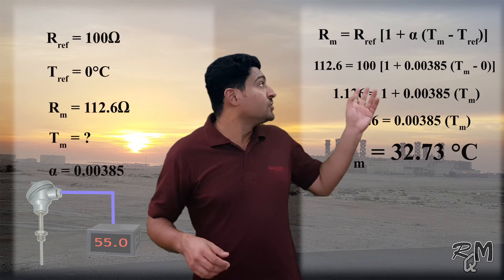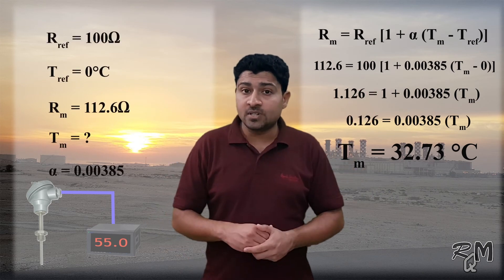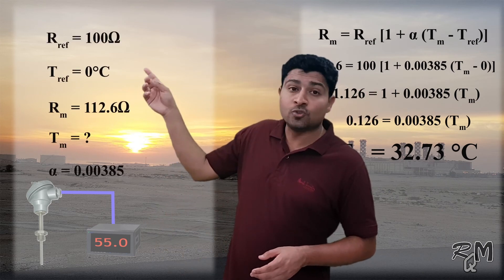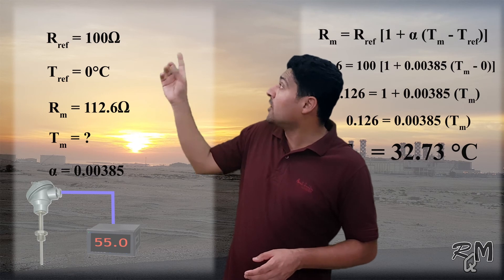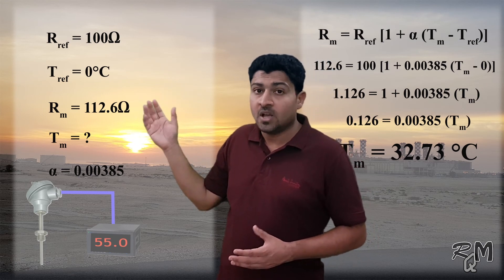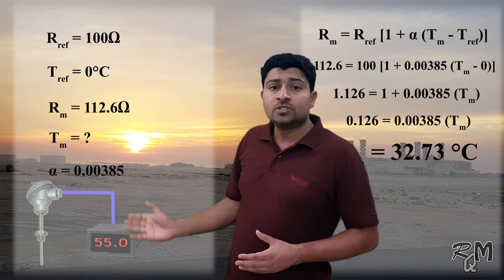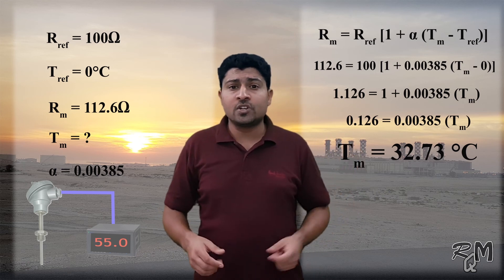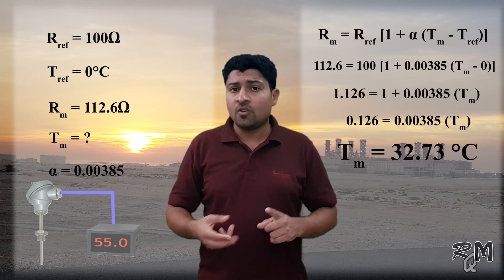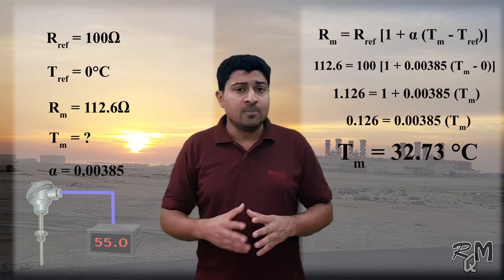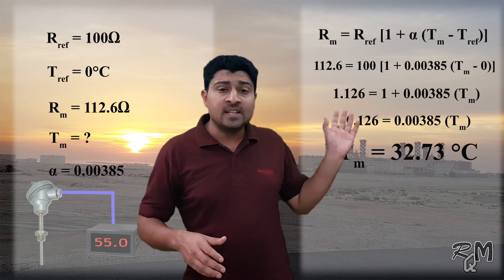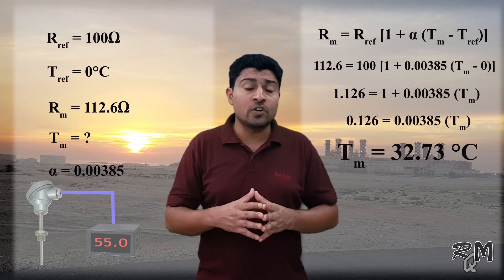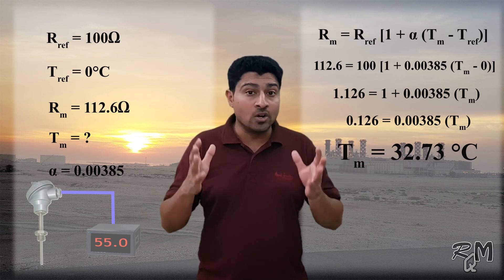You can use the same equation for PT1000 — only the reference resistance you have to change from 100 ohms to 1000 ohms, all other values will remain the same. You can also use the same equation for PT50 and PT500. I am sure if you apply this equation one or two times, you will memorize it for a long time.